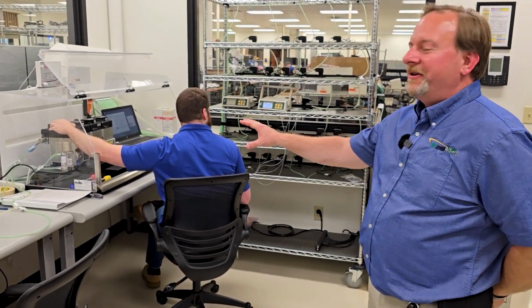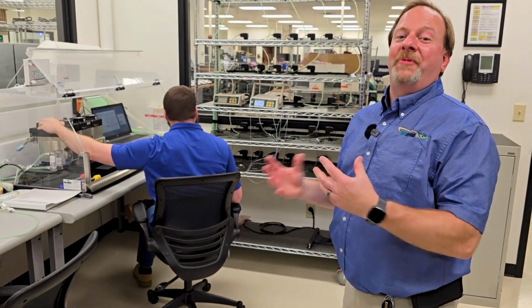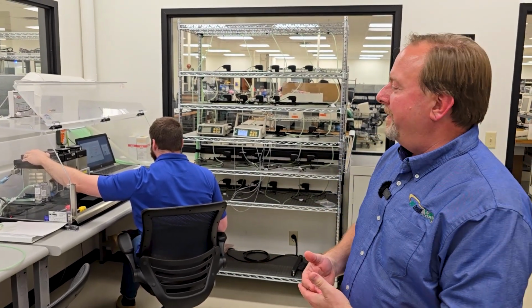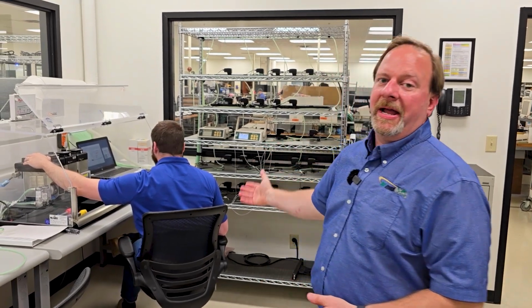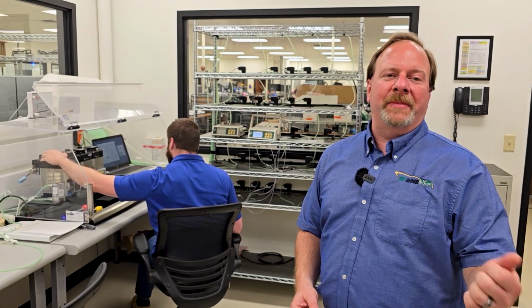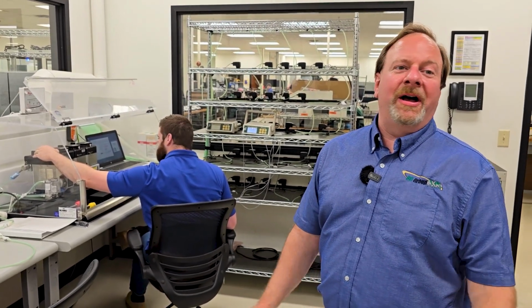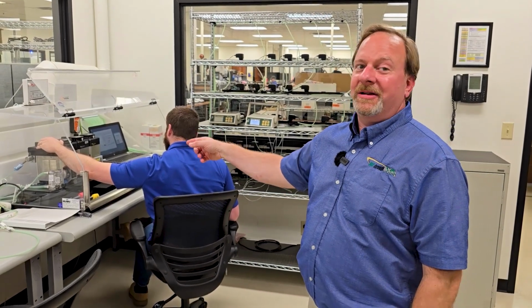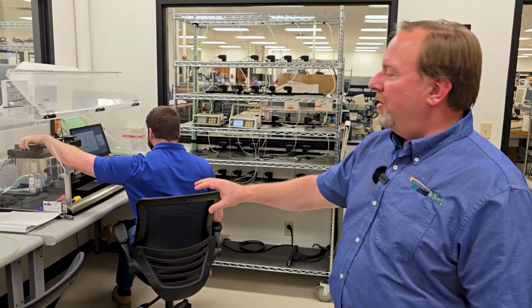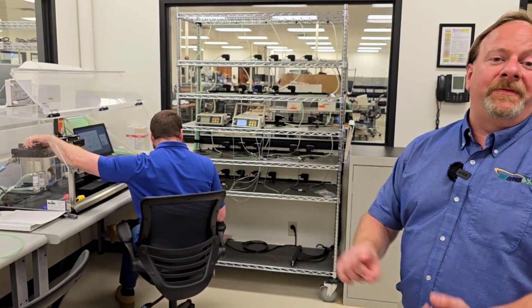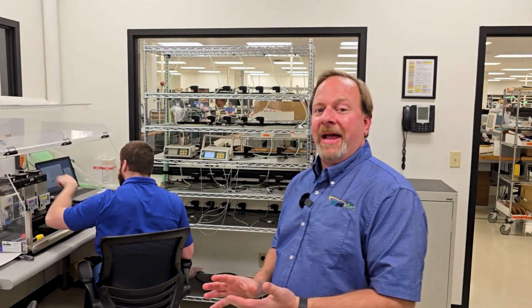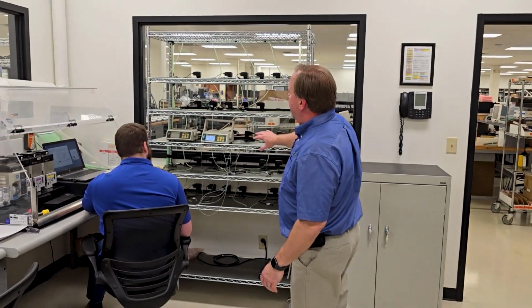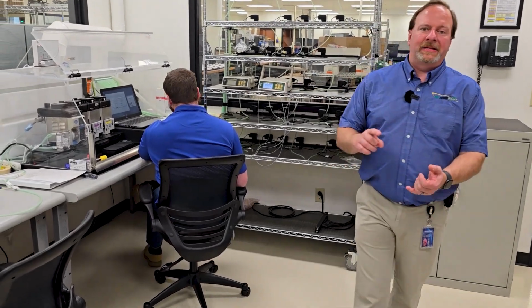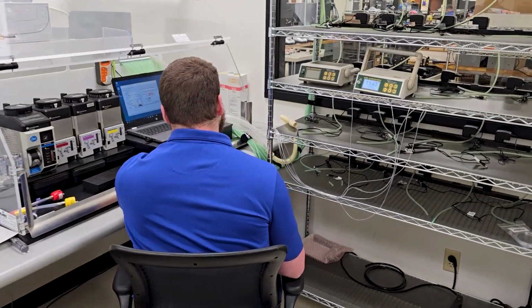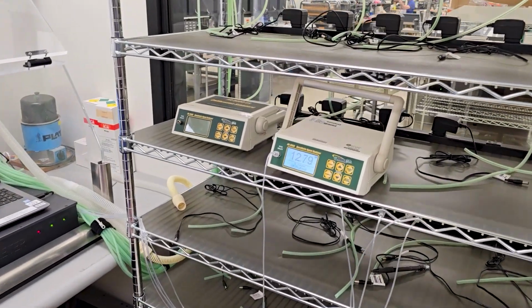Do you actually test anesthesia vaporizers? This is a very unique test station, and this is, again, a prime example of why we have engineering in the company, why we're so integrated. If we're going to make a device that can measure anesthetic agent, how do you test that? Some companies say, well, hook it up to CO2 and that's all you need. We say, no, that's not good enough. If they're going to test it with DES, ISO, SEVO, we're going to test it with that. So we have a full gas refractometer. We can do a full 12-point calibration, measuring all the gases that you would use on the anesthetic agent analyzer. This is our AA8000. We can also test other manufacturers, the Riken, and we can give you a full calibration on those devices.